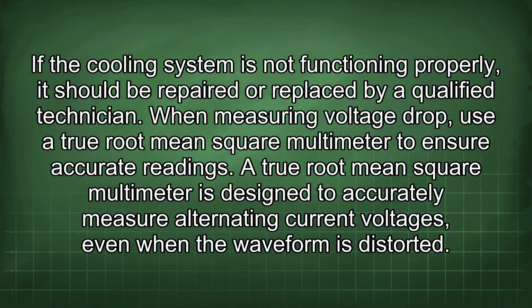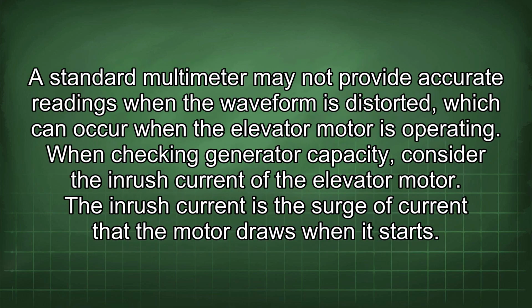When measuring voltage drop, use a true root mean square multimeter to ensure accurate readings. A true root mean square multimeter is designed to accurately measure alternating current voltages, even when the waveform is distorted. A standard multimeter may not provide accurate readings when the waveform is distorted, which can occur when the elevator motor is operating.